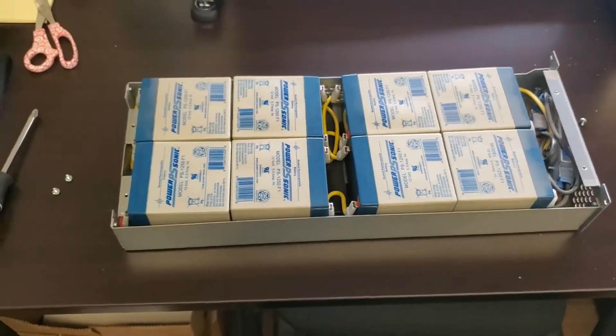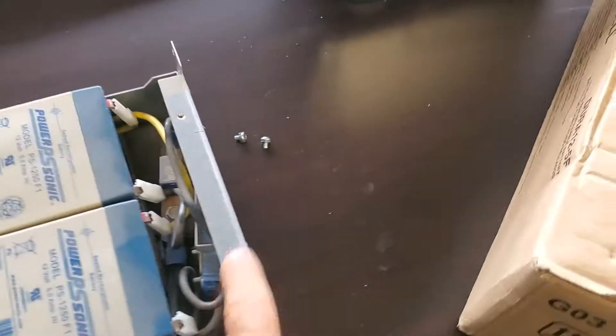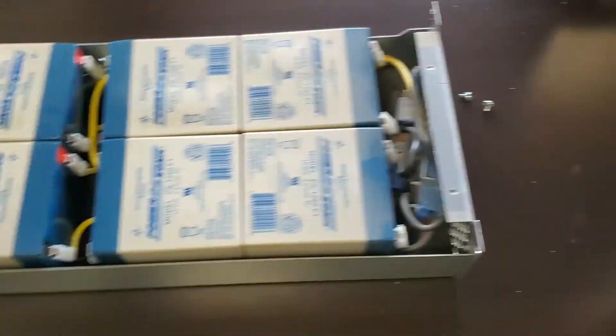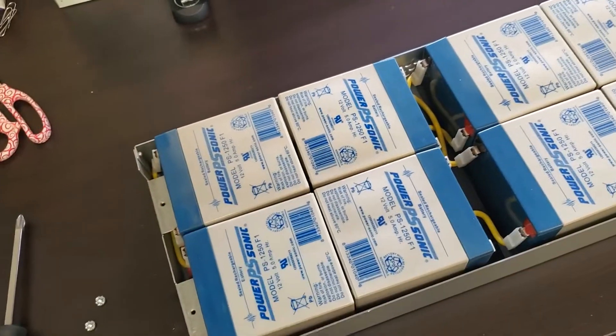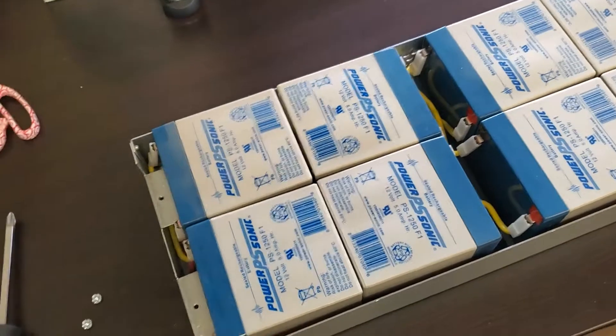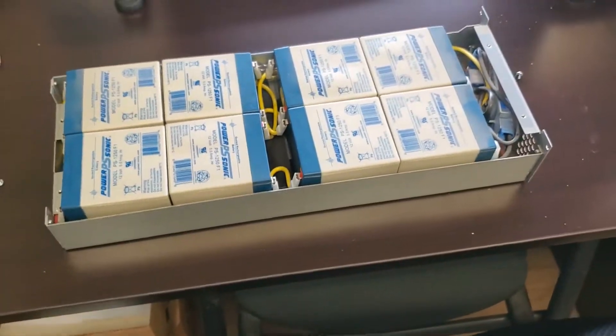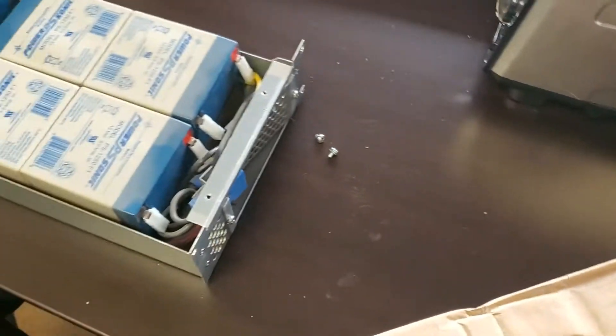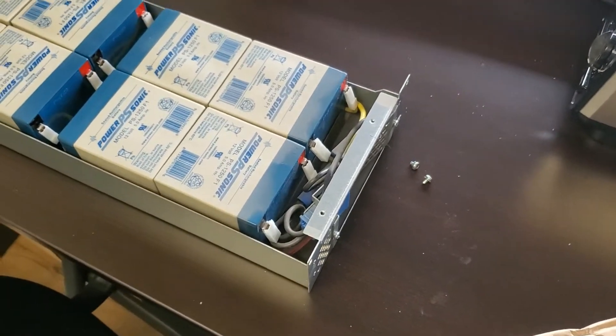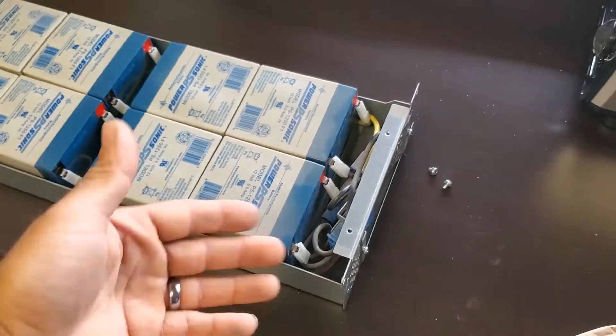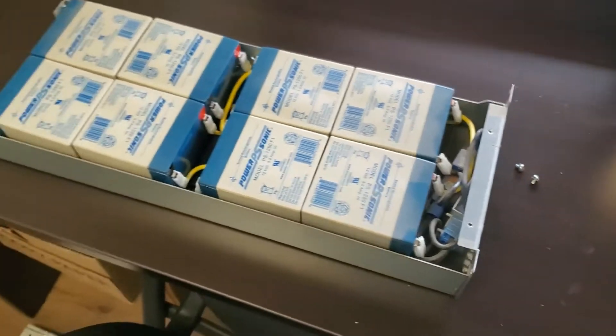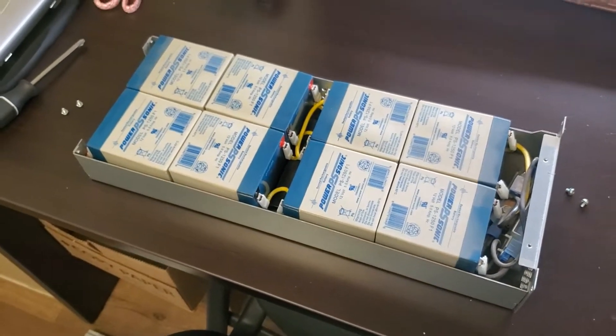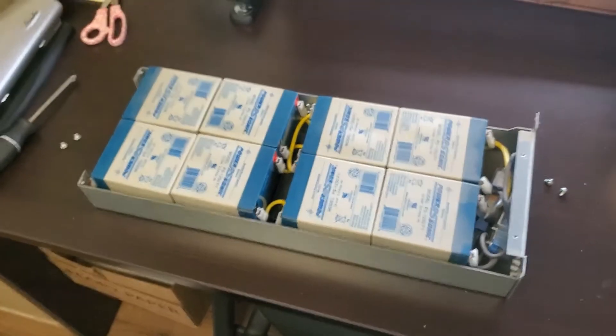I'll start replacing them. My suggestion is, now that there's no load on it, you could do just one at a time, and you just disconnect and reconnect the new one. That way you don't get them backwards or anything. In the end, you could always test at the outlet. As long as you get 48 volts, or if they're 12.5 each, you may get a little bit more. We're going to start replacing them.